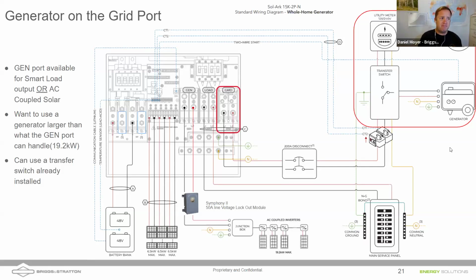We did have one question: is there any use case your team has seen of someone using a Briggs portable in a whole home backup system? I'll say this - my mother-in-law actually has a portable generator, a quite large one, maybe 10 kilowatts. It's not 2-wire start, but it does have a button to at least crank it. She has a twist lock, 50 amp twist lock on the outside of the house, with a manual transfer switch, and we're able to back up the home. Keep in mind she has gas range, gas furnace, gas water heater. So if you look carefully at those loads, it's possible to back up an entire home using a portable, but you want to look carefully at what you've got going so you're not overloading that generator.